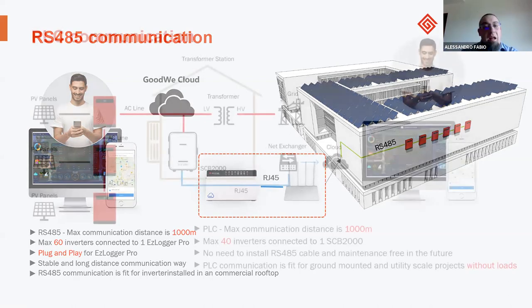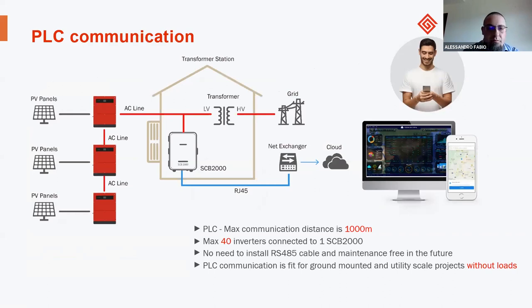For large-scale inverters or large-scale PV systems, there is PLC communication. PLC is power line communication. The maximum communication distance is 1,000 meters. The maximum number of inverters that can be connected is 40, and the name is SCB-2000. So they don't need RS-485 cable installation, but you communicate through the AC line. This is a really big advantage because it's a cheaper solution that you can use for the monitoring system.